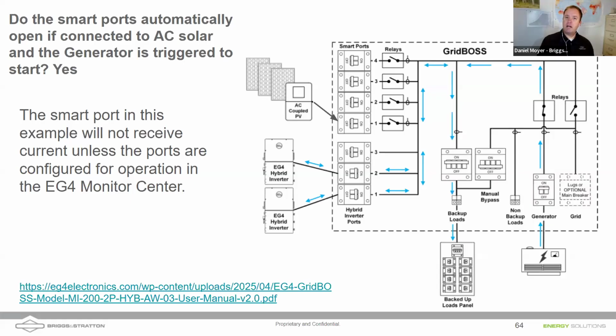One way we've historically done this in the past is we could maybe program the generator to only run at night. We could install a relay, which would open up the AC coming from the AC coupled solar so that when the generator was running, the AC coupled solar would not be producing. The Grid Boss has that built in. We have that relay right here. When that generator starts, it's going to come up, power all backed up loads. It's going to start feeding power back to the EG4 inverters with the batteries, which would be right here to the left of them. And it would open up these smart ports so that we're not allowing the AC coupled solar to recognize the generator sine wave as grid and start to backfeed that generator.